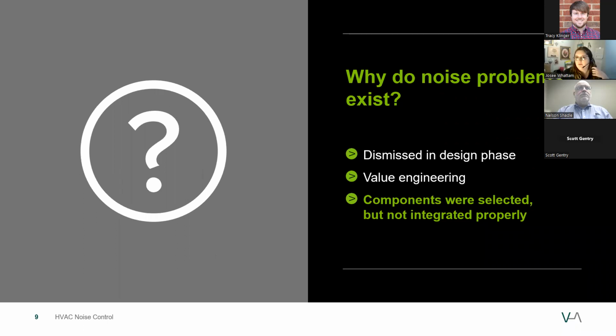To answer this question, I will refer to possibly the most influential book on noise and vibration control. You might have heard of it. It's called the Practical Guide to Noise and Vibration Control for HVAC Systems by Mark E. Schaefer in conjunction with ASHRAE. In his analysis, he describes three main reasons for noise problems in HVAC systems. Today, we're primarily going to focus on number 3, which is components were selected but not integrated properly. However, before we get there, let's address item number one, which is dismissing noise control during the design stage, or item number 2, which is post-design cost cutting, aka value engineering.